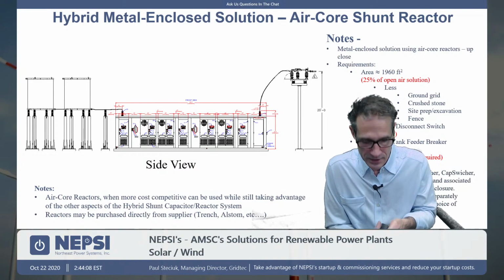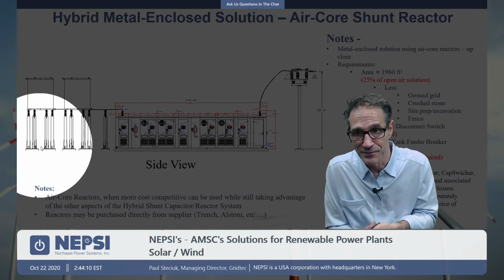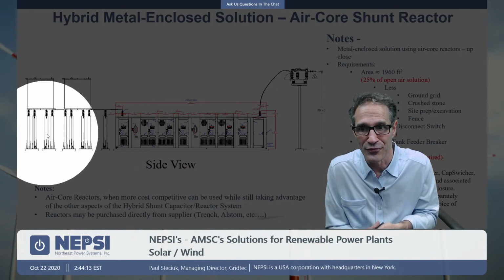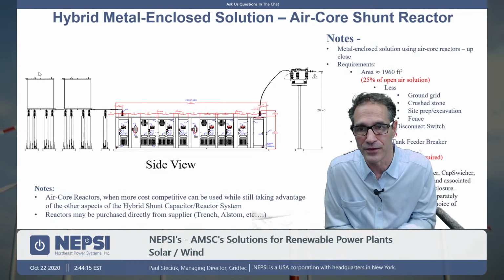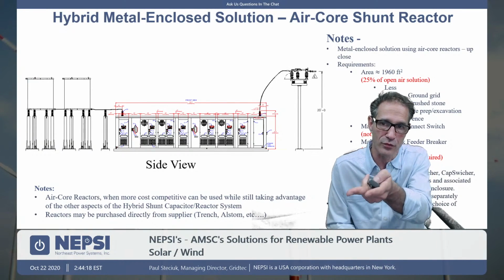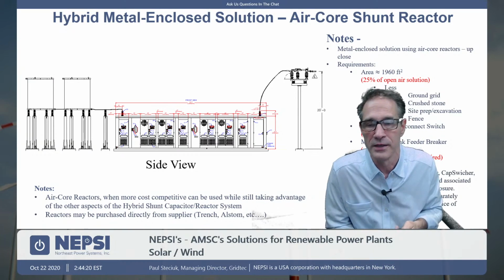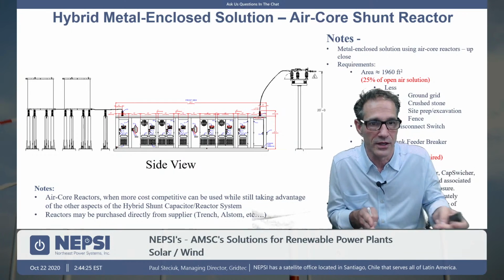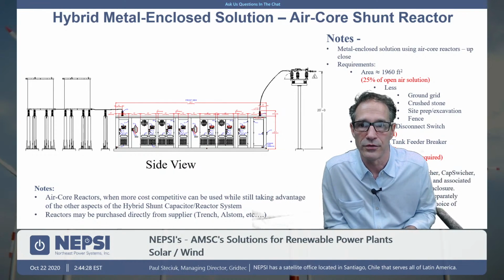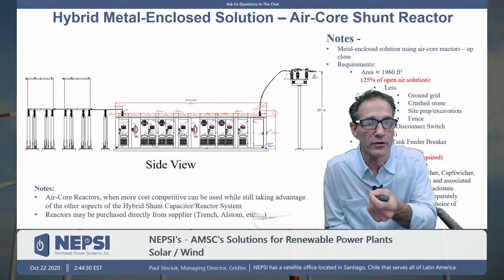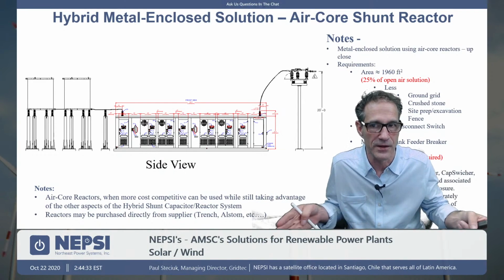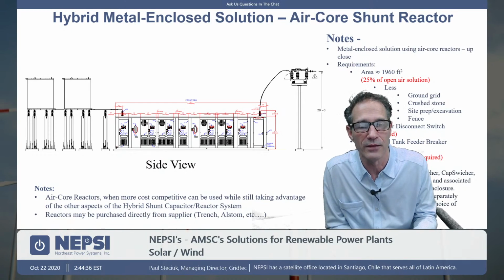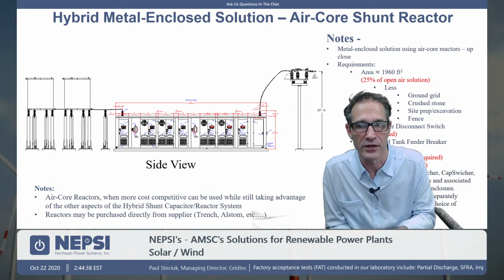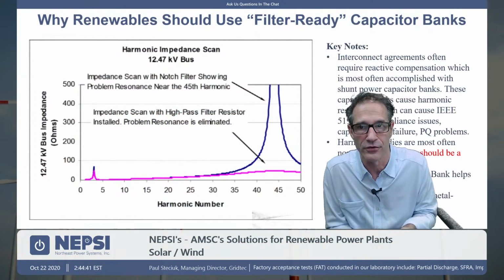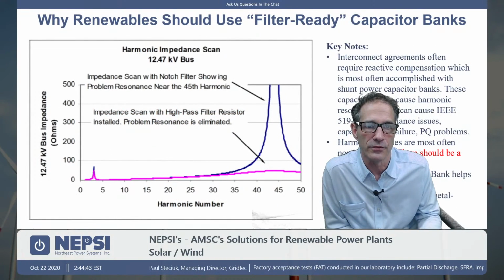If you want to keep the project as competitive as possible, then go with these air core reactors. You can see here the size of these air core reactors. They're really large in size. And there's 3 reactors, 2 in the front and 1 in the back, kind of in a triangular format. One of the things about air core reactors is you've got the magnetic field that you need to be concerned about. So you need to have spacing between where the reactors are and all metal parts that form closed loops. And that spacing factor is typically 1 times the diameter of the reactor away from the reactor area. So it can be quite a large area that you're dealing with.